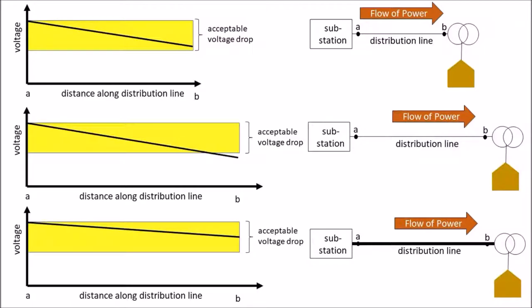In this situation, the design is sufficient to deliver power at the proper voltage to the community at the end of the line. The middle diagram shows a community that is further away, point B is further from point A than in the top diagram, and we can see that the line voltage is now actually lower than the acceptable voltage drop. This would be a bad condition, a poor design.